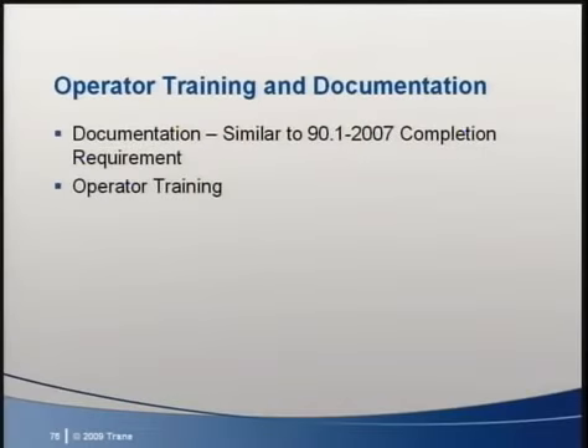In the Core Performance Guide, there are requirements for documentation, as there are in ASHRAE 90.1 2007 in the completion requirements section. By the way, you may want to see if you're following the ASHRAE requirements, since they're required by EA Prerequisite 2. In addition to these, the Core Performance Guide requires operator training, including a formal walkthrough and training session to give building operations team hands-on experience and the chance to ask questions.